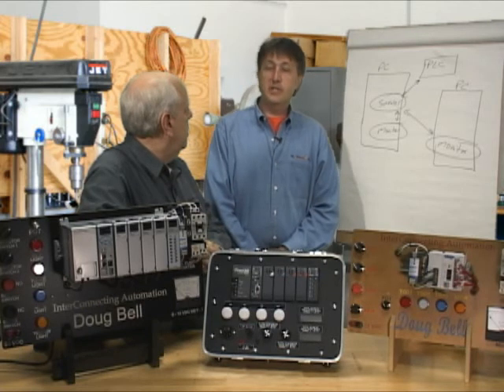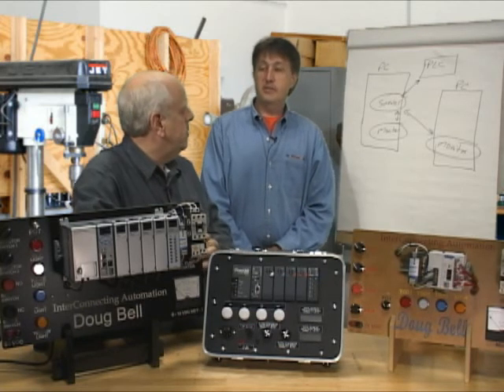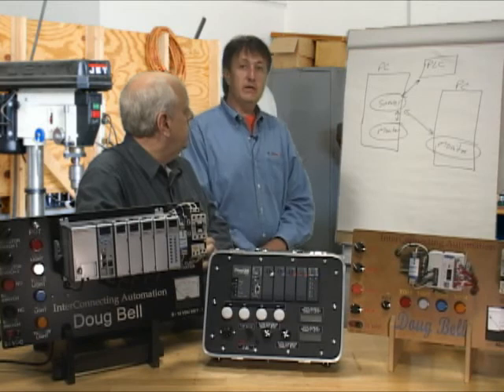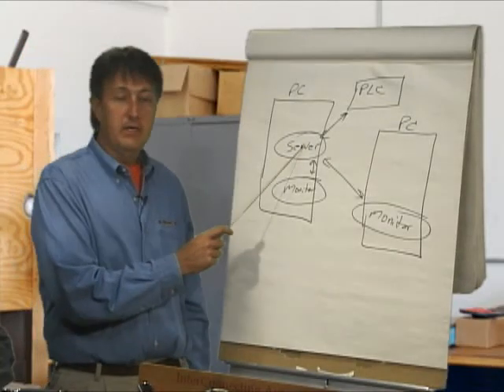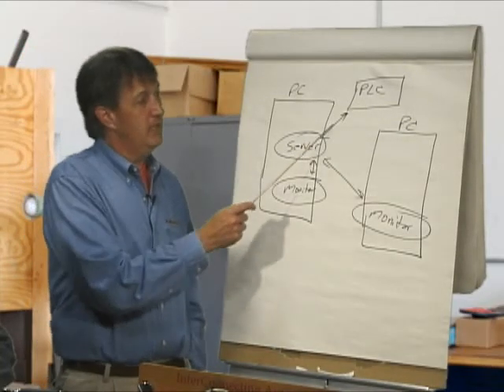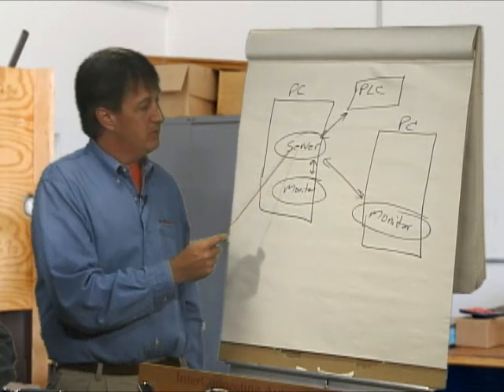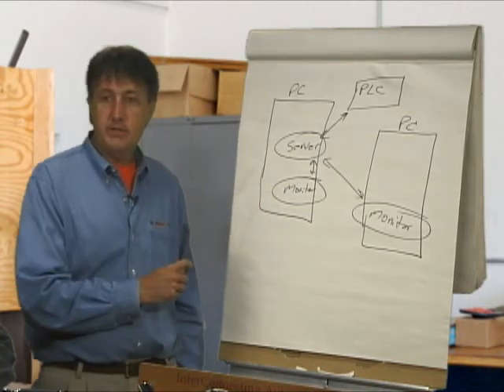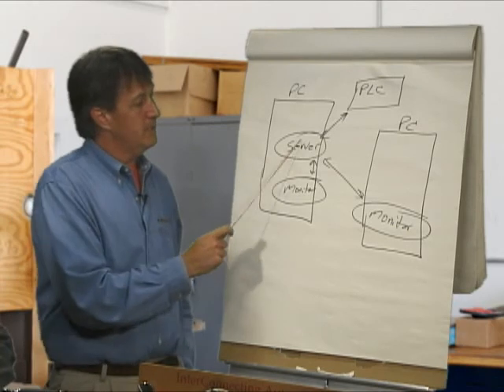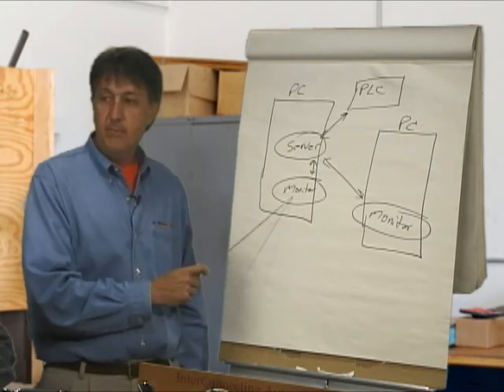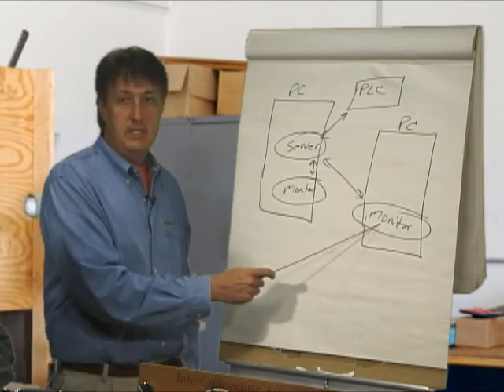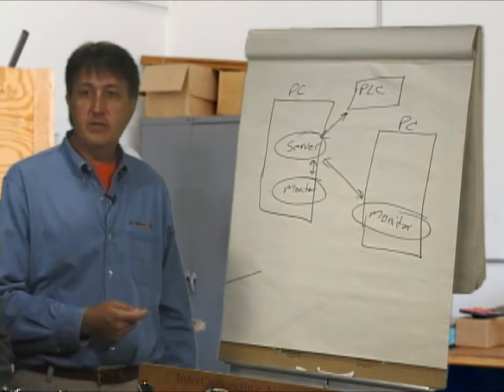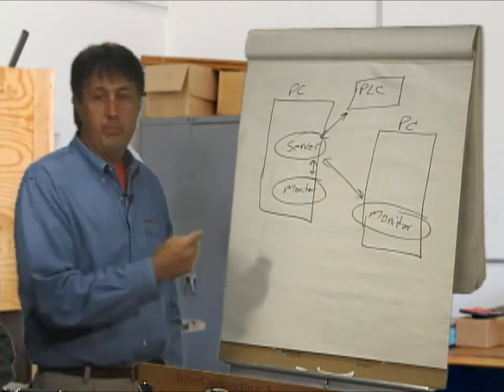DataWorks is made up of two separate versions: DataWorks Standard and DataWorks Pro. Looking at DataWorks Standard, it's a piece of software that runs on a PC that listens for the PLC to send information to it, and then we can store that to a text file. It's made up of a server and a monitor piece. The server runs on a PC, the monitor can run on the same PC or a different PC, and the monitor allows you to configure the server and also monitor its progress whenever it's listening for PLC information.